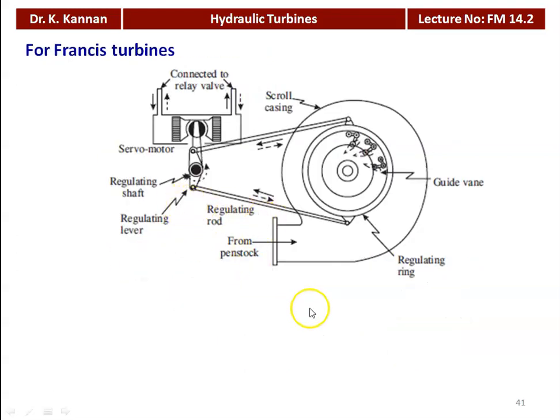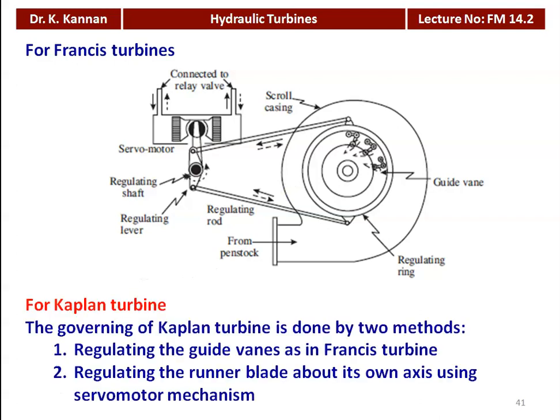In the case of the Francis turbine, the entire governing mechanism is connected to the servo motor, which regulates the guide vanes of the runner. The position of the guide vanes is changed by means of the servo motor via a regulating lever and regulating shaft, so that the amount of water admitted to the turbine is regulated according to the load. For the Kaplan turbine, there are two methods of governing: regulating the guide vanes as in the Francis turbine, and regulating the runner blade about its own axis using the servo motor mechanism. The governing mechanism is inbuilt with the turbine for regulating the power produced.